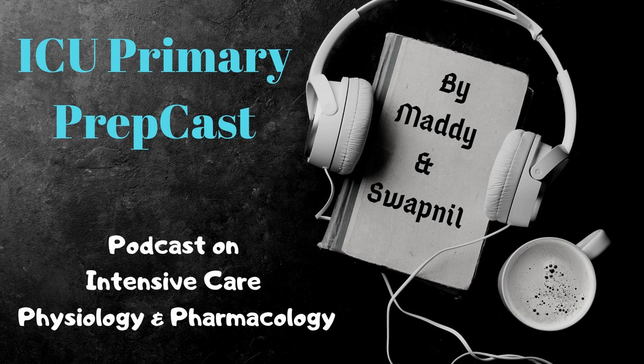So the components of it are a piece of short, stiff tubing to maximise the transfer of the information in the arterial waveform to the transducer with minimal loss of wave information. And then there's essentially a Wheatstone bridge connection of little silicon crystals. And that's the same in any invasive pressure monitoring system, but in this case, we're talking about arterial waveforms. And then that will be converted into waveforms that are subsequently put through various filters to remove some of the signal abnormalities. So the short, stiff tubing is there to optimize the transfer of the harmonics of the waveform.